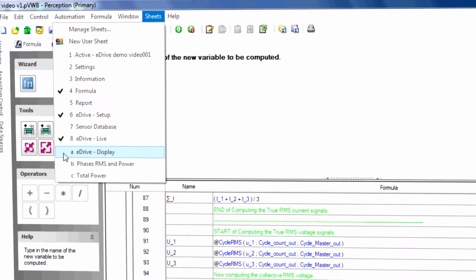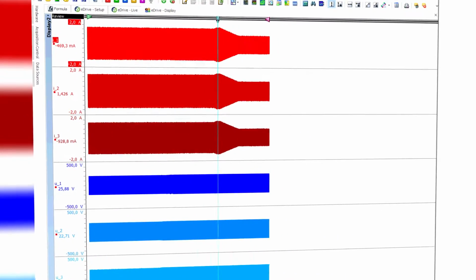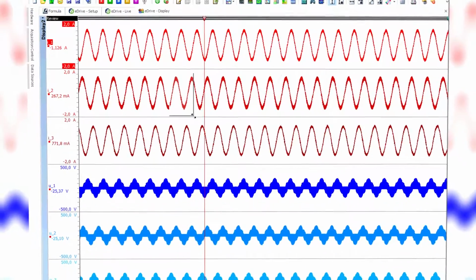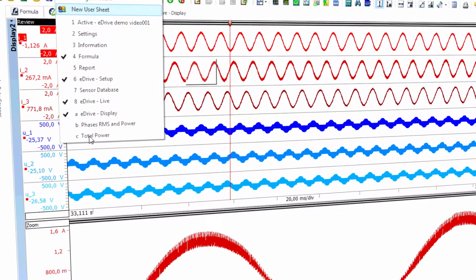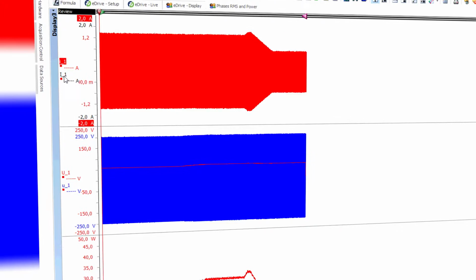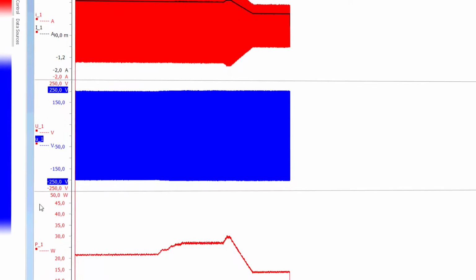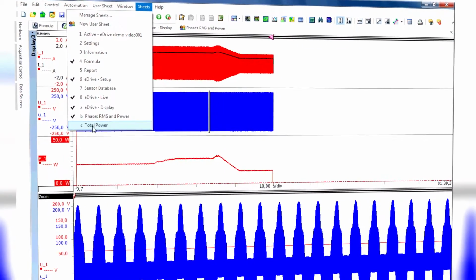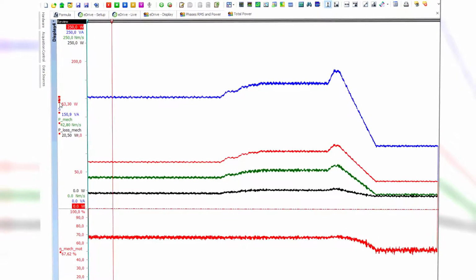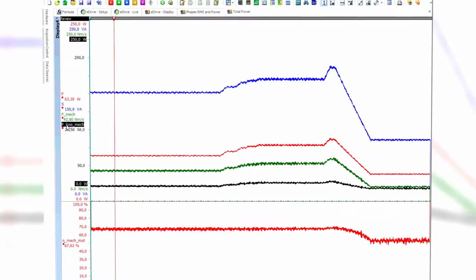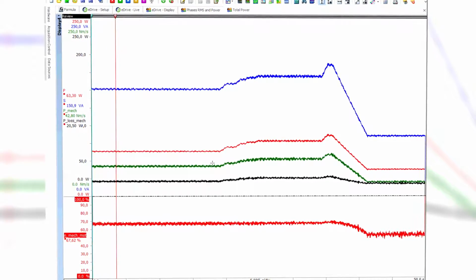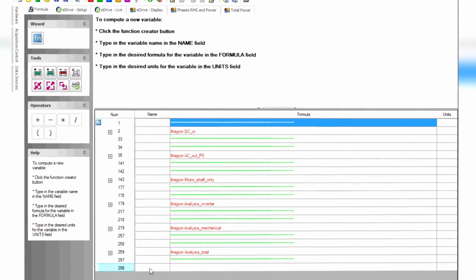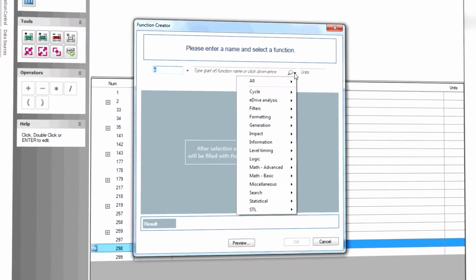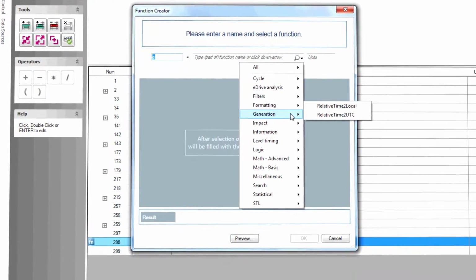We start the review using the display sheet. It shows raw data for visual inspection with scroll, zoom, and cursor. Sheet Phase RMS and Power shows all entities of Phase 1 like voltage and RMS voltage, current and RMS current, and finally, true power in Phase 1. The sheet Total Power shows true and apparent power at the inverter output, the mechanical power, and the power loss in the motor. Finally, the motor efficiency is shown as a trace over time through the 3 set points we have recorded. All of that is available out of the box, no user programming required. But this is where the real journey starts. Based on the raw data, the nearly unlimited capabilities and the more than 200 functions in the formula database, the user can proceed with any analysis he wants to do.